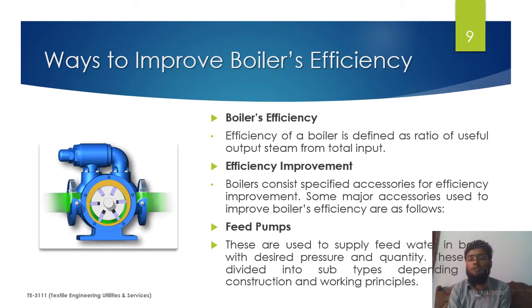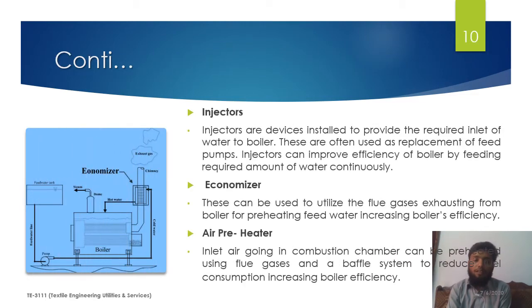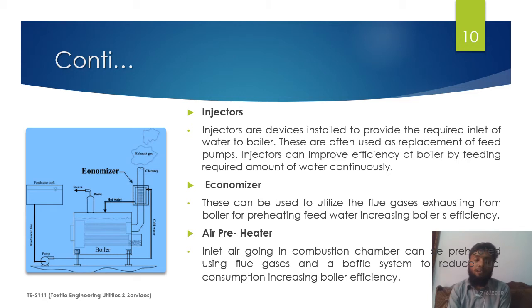The second accessory is injectors. Injectors are devices used for providing high-pressure water of the required quality to the boiler, and these are often used as a replacement for feed pumps. The third accessory is economizers — these are installed around the chimney of the boiler and are used for utilizing flue gases from the boiler and preheating the feed water.